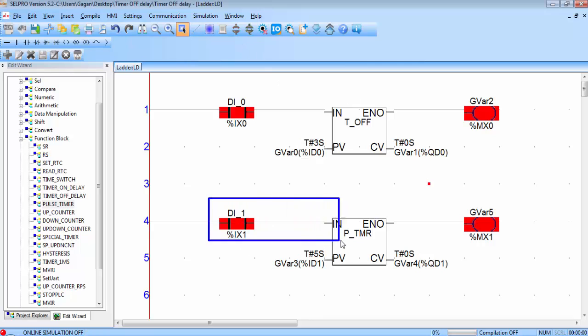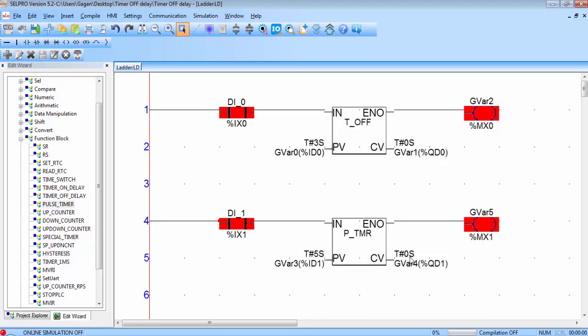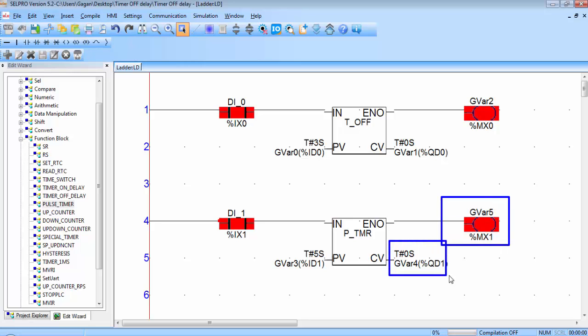To activate the pulse timer we have to provide a pulse to its IN pin, that's why its name is pulse timer. To provide a high to low pulse for this timer, double click on this contact and again double click on the contact. You can see the status of coil is on and CV is counting the time. When CV is equal to PV it will turn off the output and CV will again come back to zero.